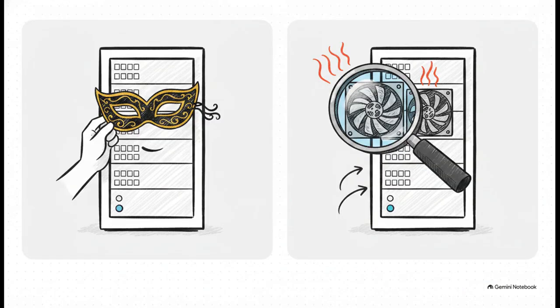Just look at what happens when you actually fix that math. A facility might proudly claim a nameplate air-cooled PUE of 1.25, but when you strip away the disguise and correctly label the power drawn by those embedded fans as infrastructure cooling instead of IT compute, the actual PUE of that air-cooled facility jumps all the way up to 1.43.